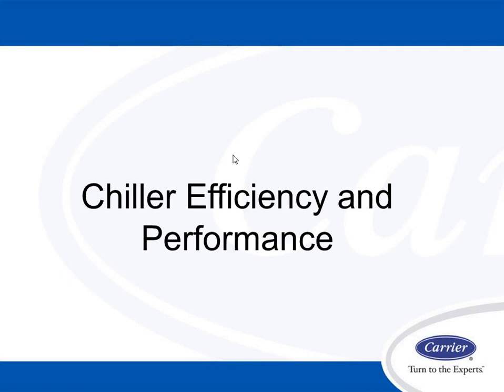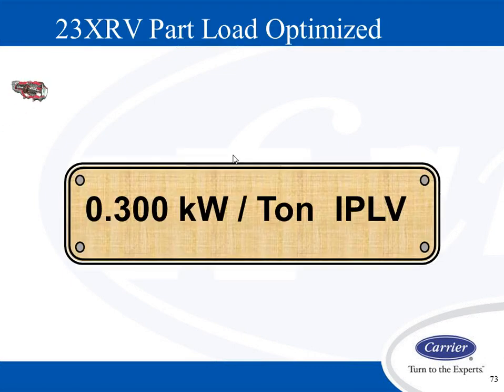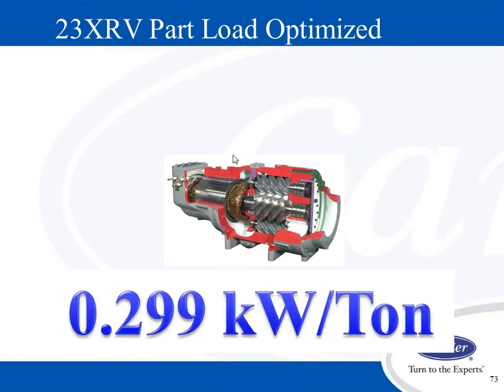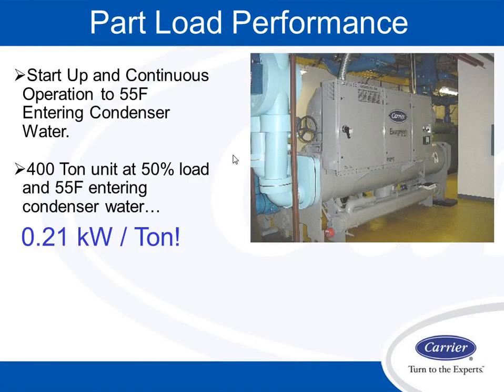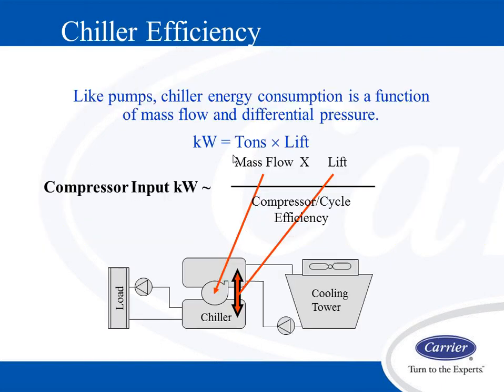Let's talk a little bit about chiller efficiencies and performance. I mentioned before that we broke the 0.3 kW efficiency barrier with IPLV. Now we have a snapshot of one machine operating in Charlotte with continuous operation, 55-degree entering condenser water, with measured part load values at 50% load, at 0.21 kW per ton. This is an actual installed kW per ton in an actual install in Charlotte, North Carolina.